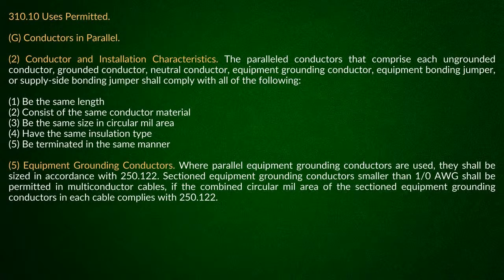This is not even ambiguous. And you go over there, the equipment grounding conductor is based on what? The size of the overcurrent protection device. It doesn't say anything about the circular mil except for if it's in what? A multi-conductor cable. Yeah, and I think this is funny because I think he says in here that you can't even do a cable. Oh, well, I didn't hear. Well, we might hear that on next.